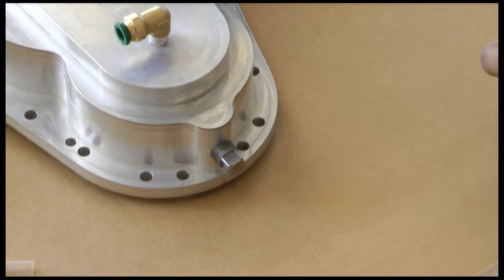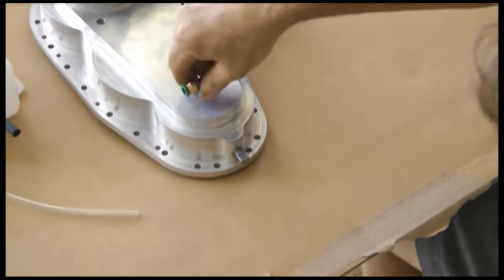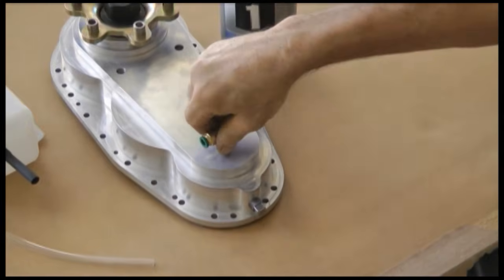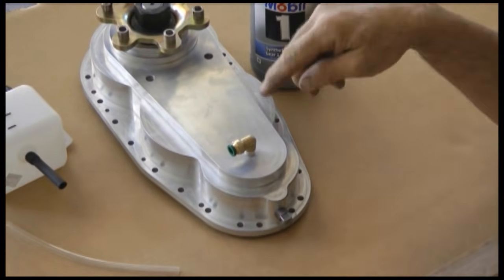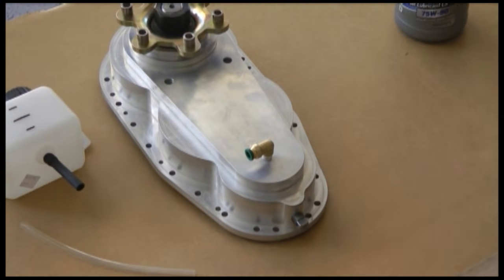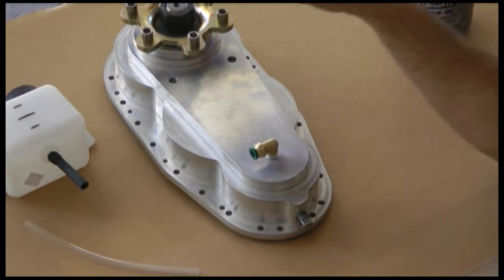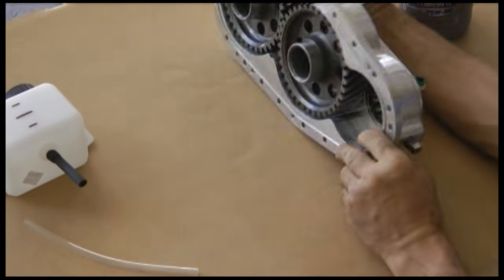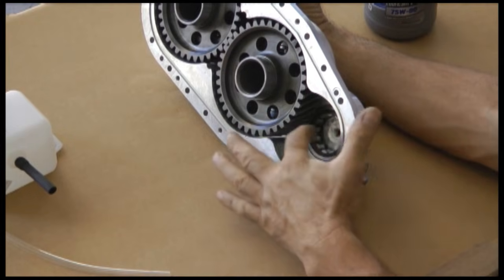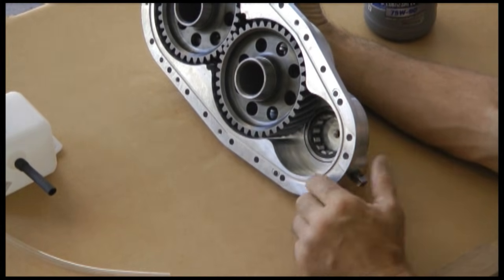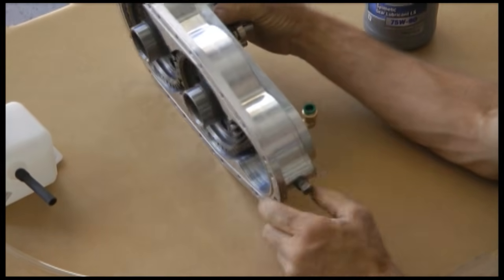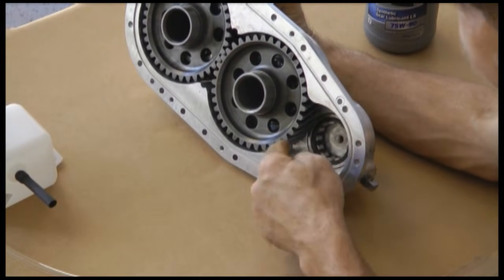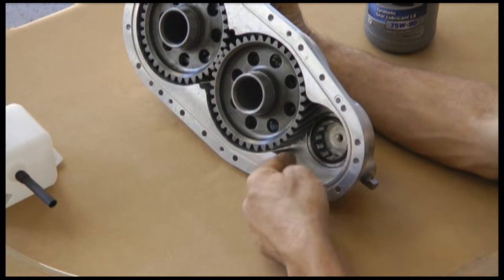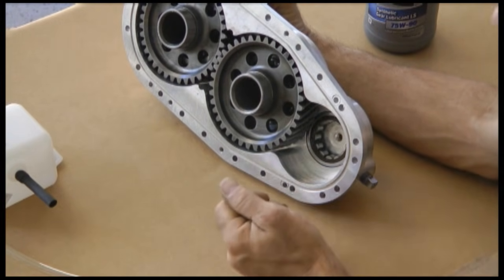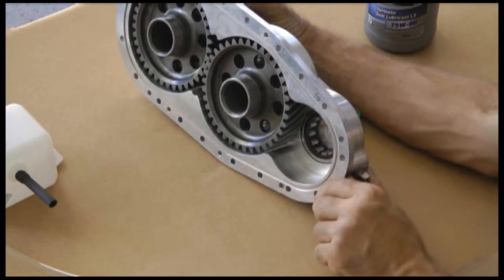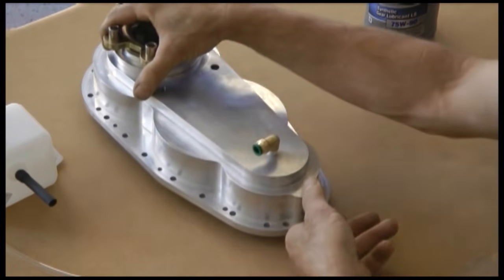Here's a fitting that's provided and screwed into your gearbox. This vents the gearbox from a location internal to the input gear. The input gear is hollow, and the nice thing about venting it right there is that there's no centrifugal motion from the gears to force oil out of the gearbox. So it's an ideal location for venting.